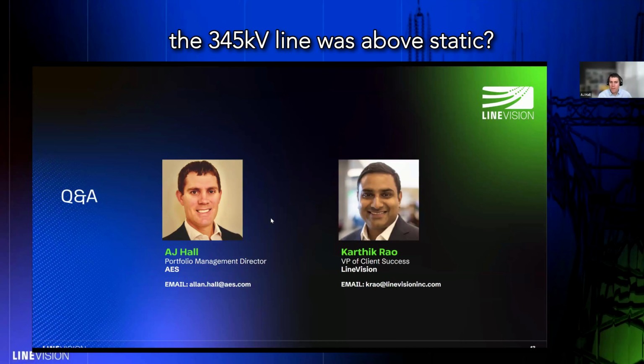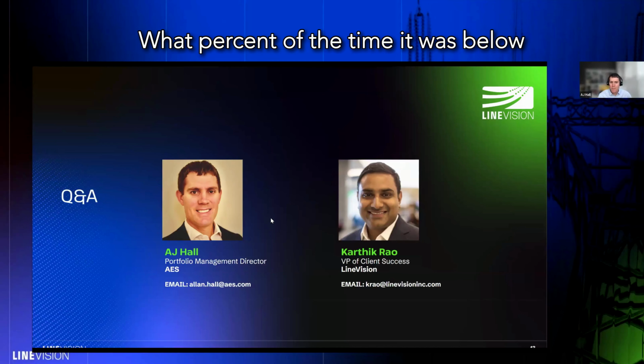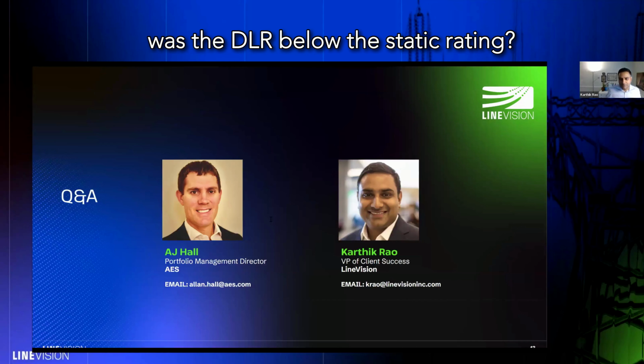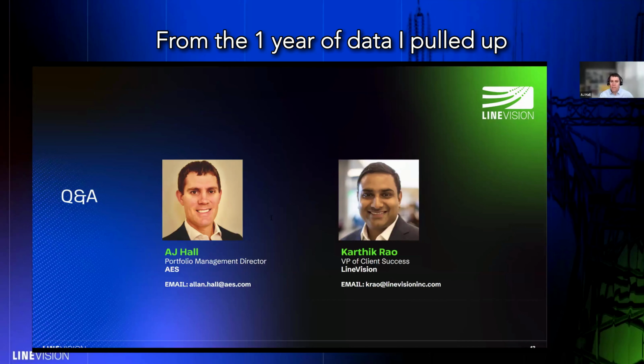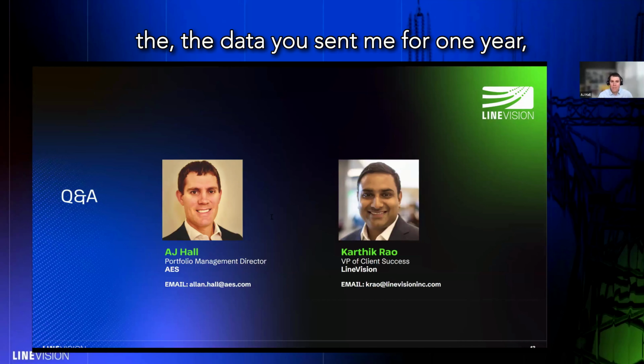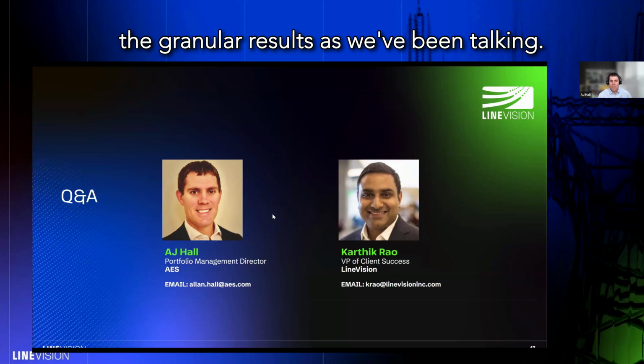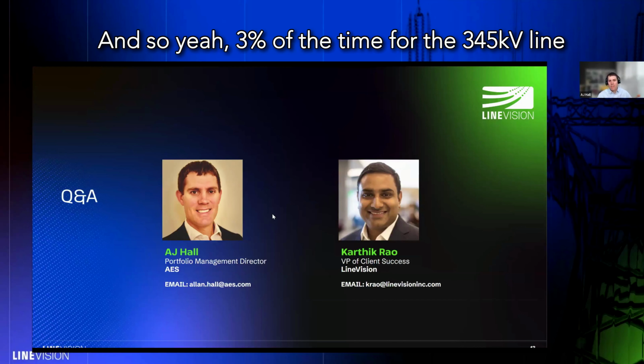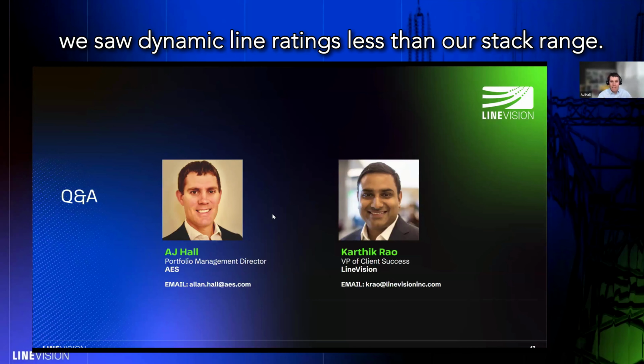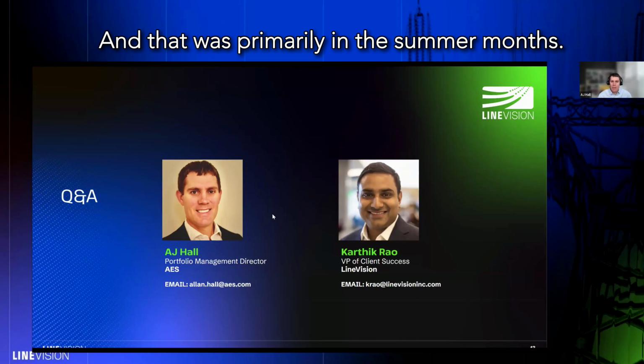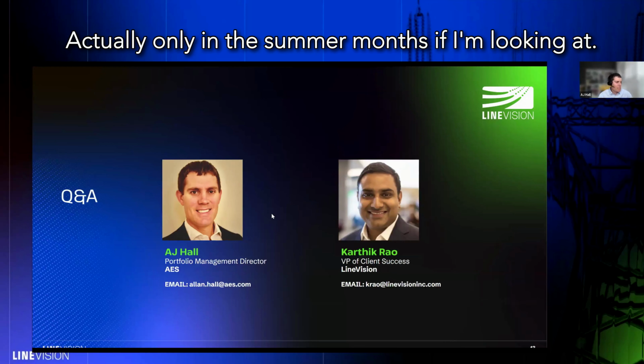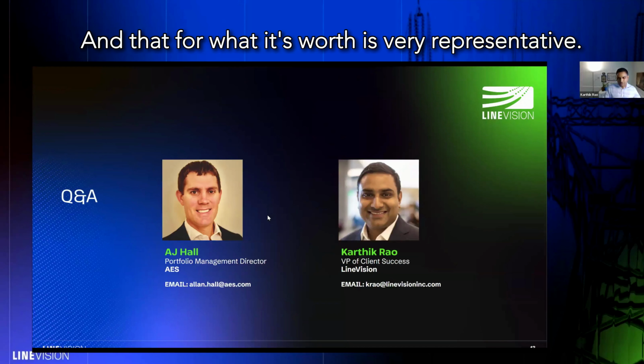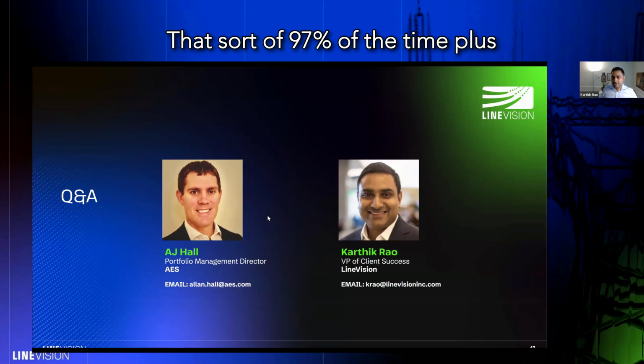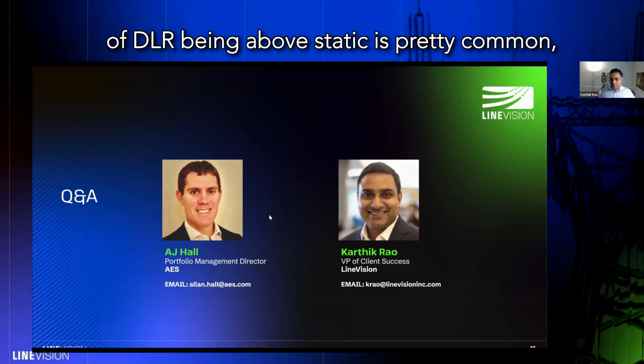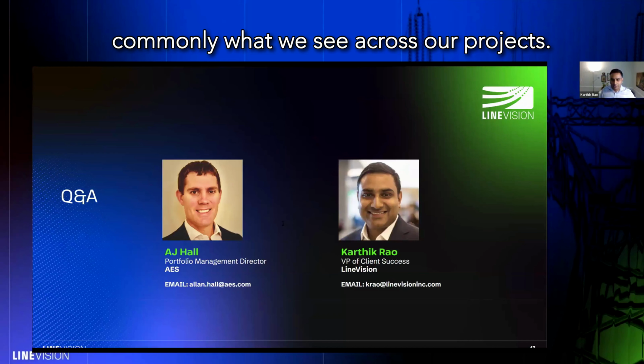So what percent of the time was the DLR below the static rating on the 345 kV line? 3% from the one year of data. I pulled up the data you sent me for one year of granular results, and yes, 3% of the time for the 345 kV line we saw dynamic line ratings less than our static rating, primarily in the summer months, actually only in the summer months. For what it's worth, that's very representative: DLR being above static 97% of the time or more is pretty commonly what we see across our projects.